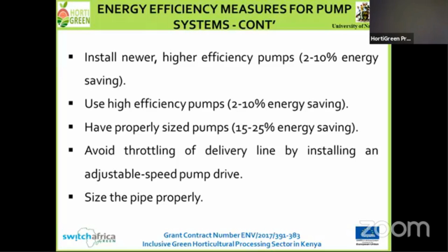And so I've talked about sizing, avoiding throttling of the delivery line. Instead of having a valve on the delivery line to control the capacity of flow rate, it is better to have an adjustable speed pump drive. And even the pipes through which the fluid is pumped need to be properly sized. If they are too narrow, resistance to flow is too high, and higher energy consumption is incurred.